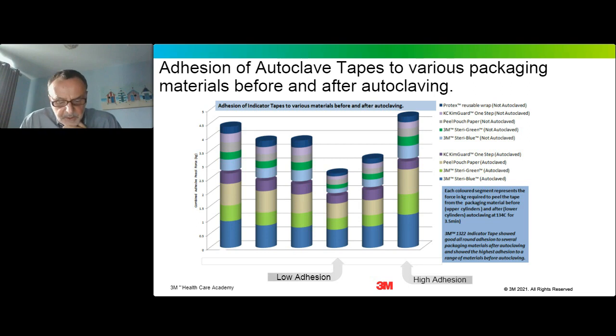It can also be seen that none of the tapes adhered particularly well to the reusable non-cotton-based material. It should be noted that this had a very shiny surface. That's the very top blue bar on all of the columns. It's the Protex reusable wrap. So you can see that because they are very thin slices, the peel strength was relatively low. So the tapes were not sticking particularly well to that material. And as I say, this is because it had a very shiny surface, and so it was difficult for the tapes to grab onto that surface.